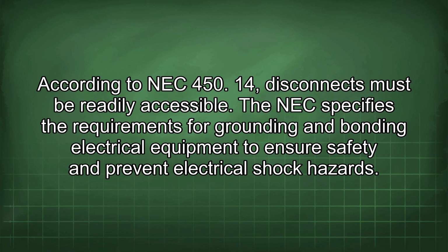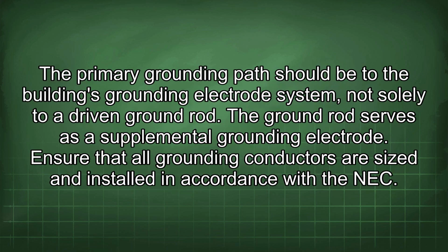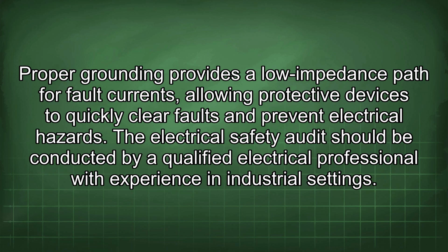The NEC specifies the requirements for grounding and bonding electrical equipment to ensure safety and prevent electrical shock hazards. The primary grounding path should be to the building's grounding electrode system, not solely to a driven ground rod. The ground rod serves as a supplemental grounding electrode. Ensure that all grounding conductors are sized and installed in accordance with the NEC. Proper grounding provides a low impedance path for fault currents, allowing protective devices to quickly clear faults and prevent electrical hazards.